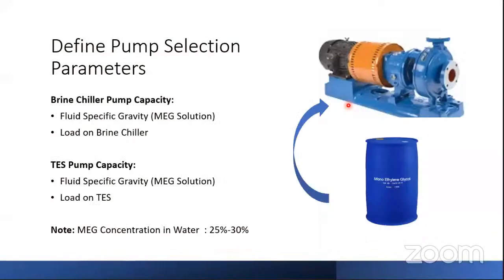Pump selection parameters, these also we need to give to the pump guy, that this is the kind of pump that you have to come up with. We need to specify the fluid kind. We need to tell him that this is the fluid that we are using, and this is going to be the specific gravity, so that he can apply the density correction while selecting his pump. Of course, the head will matter, so that head calculation can be done. It is done by the software as well, but if at all it is required to be done in real time, that is also possible. So monoethylene glycol concentration in water of nearly 25 to 30% is what is generally practiced in ice thermal storage systems for comfort cooling.